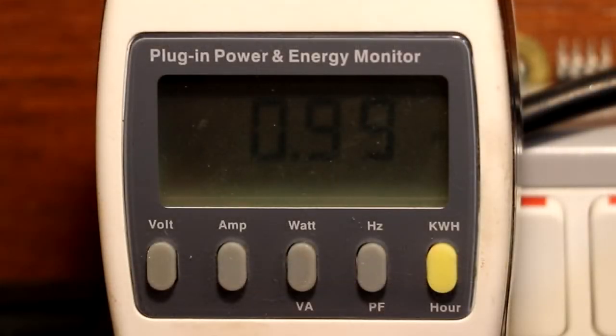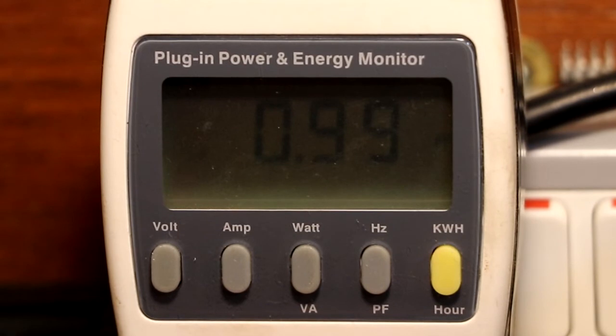So you can see we've now got a power factor of about 0.99, approaching 1. If you enter that into your calculator and hit cos to the minus 1, it gives you a phase angle between voltage and current of just 8 degrees. Our voltage and current are pretty much in phase now, and you can see on the power meter it's swinging between 0.9 and 1. Effectively our transformer doesn't look like an inductor anymore, it's looking exactly like a resistor.